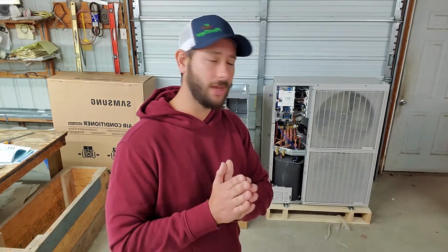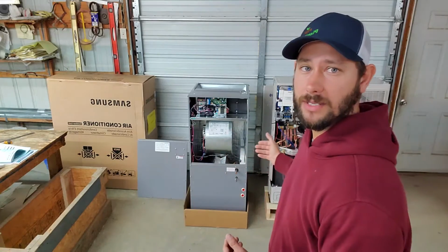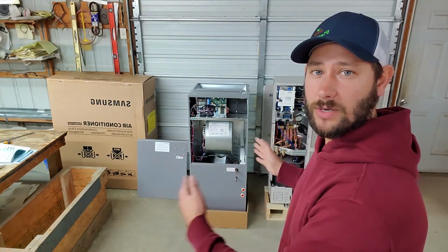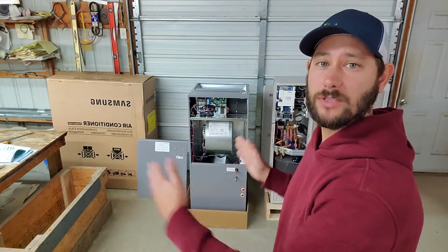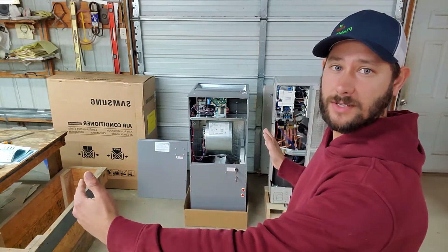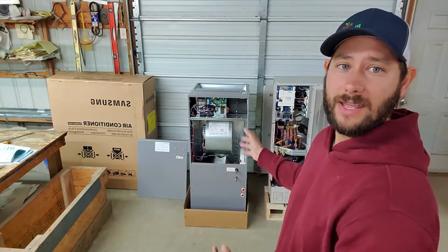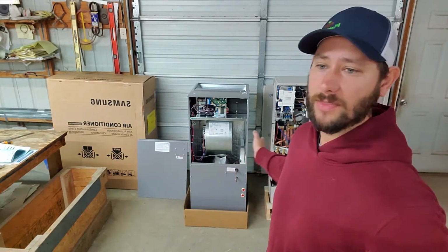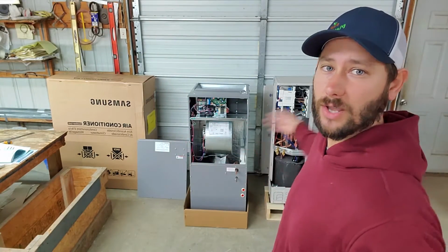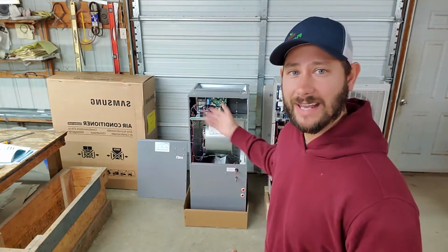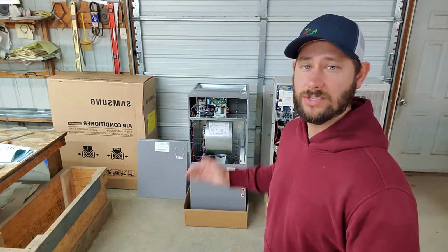All right, so let's also talk about pipe connections. I have the option now with this equipment to take my indoor and outdoor unit and separate them up to 246 feet. So I can have my indoor unit on the other side of my house and the outdoor unit on the other side, and I have more of a pipe connection length. Then I have maximum vertical separation of 98 feet for this. So it just gives me more flexibility with the installation.